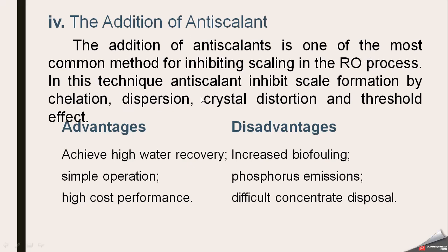In this technique, anti-scalant inhibits scale formation by chelation, dispersion, crystal distortion and threshold effect. That is, the anti-scalant molecules basically capture the calcium, magnesium or other scale-forming ions, or they disperse, so they do not allow the formation of calcium carbonate scaling or deposits, or crystal formation.